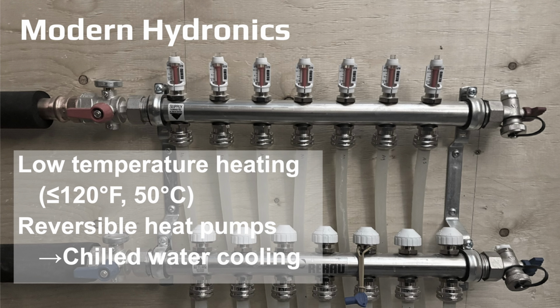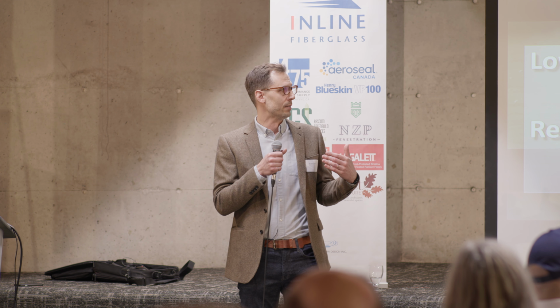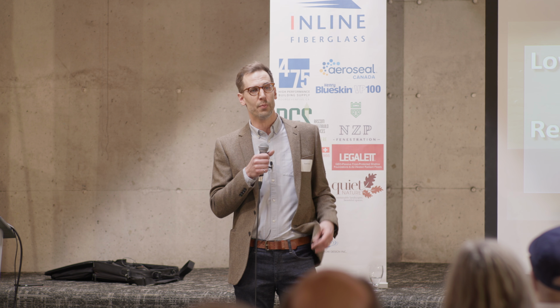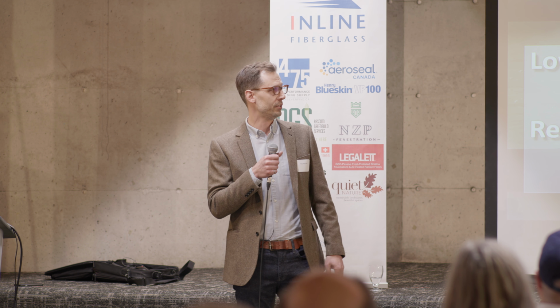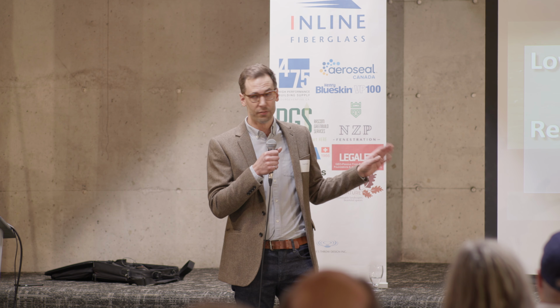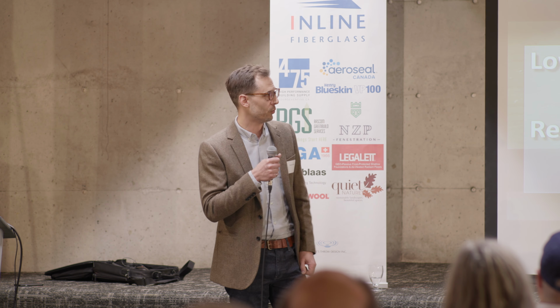The next point is a bit redundant. Heat pumps are reversible by nature, but the idea is that as we move away from boiler systems, which really only do one thing, make hot water, and use heat pumps in our hydronic systems, we now have the ability to produce chilled water and use that to cool the building too. Historically, with a custom home with in-floor heating fed by a boiler, you'd have to provide a secondary system to do the cooling. Now we have the flexibility to do that with chilled water, all with one system.